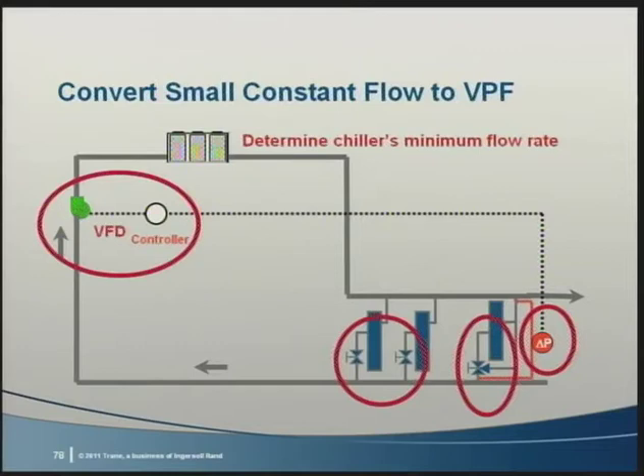A drawback is that there will always be more water being pumped than necessary, so pumping energy will be a little bit higher. But if the minimum flow rate is low, the additional pumping power will be minimal. This can work extremely well in single chiller applications because of its simplicity. Chilled water system savings for a 2-story office building in St. Louis were shown to be about 6% annually.